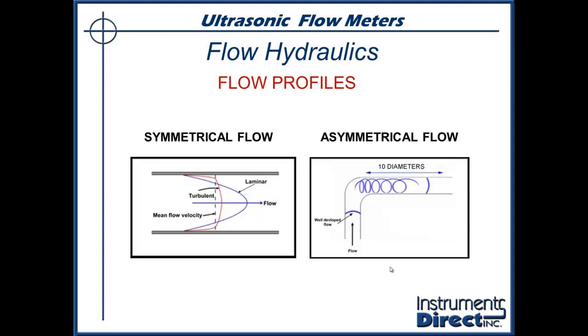You've heard the term: give me 10 to 15 pipe diameters. In this cutaway diagram, what you'd like is 10 to 15 pipe diameters of straight run pipe, and what you'll get on the inside will look like this — flow is fastest at the center and slowest near the pipe wall, just like a man in a motorboat casting a line out behind it. These elliptical shapes are defined as Reynolds numbers, and they will be more blunt or elliptical based upon the flow rate. If you draw a center line down this flow, the top half equals the bottom half.